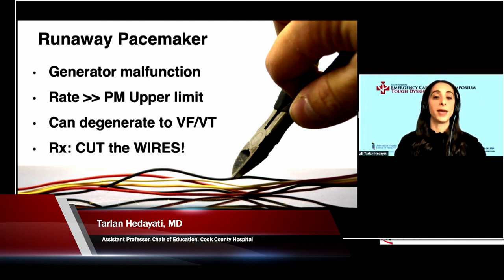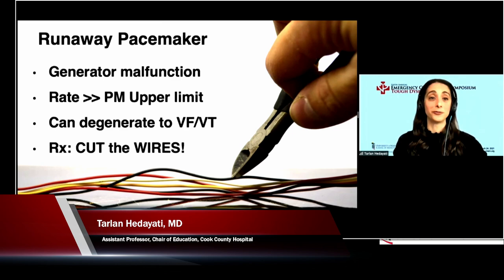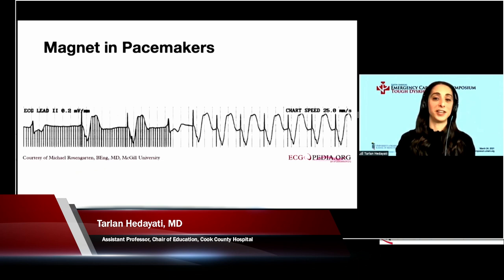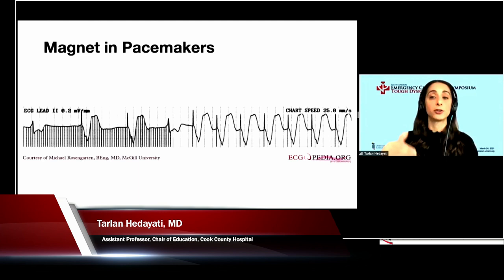And then you take over and try to make sure they continue with their normal cardiac activity afterwards. Great example of what a magnet does in a pacemaker: you can see the pacemaker firing away here, but once you place that magnet on, it fires the pacemaker up to a higher rate. So put the magnet on the pacemaker when you see a patient with symptomatic bradycardia and you know they have a pacemaker—they should be going faster.